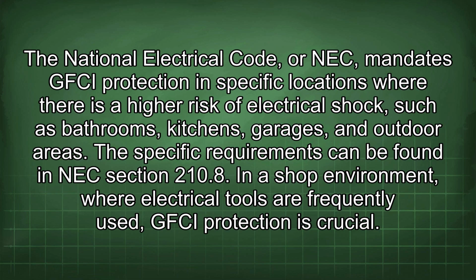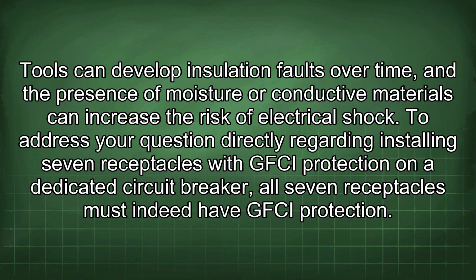The National Electrical Code, or NEC, mandates GFCI protection in specific locations where there is a higher risk of electrical shock, such as bathrooms, kitchens, garages, and outdoor areas. The specific requirements can be found in NEC Section 210.8. In a shop environment where electrical tools are frequently used, GFCI protection is crucial.